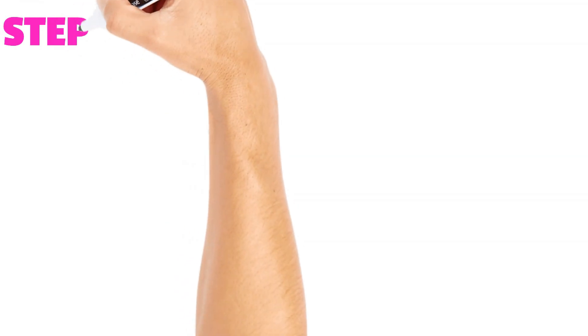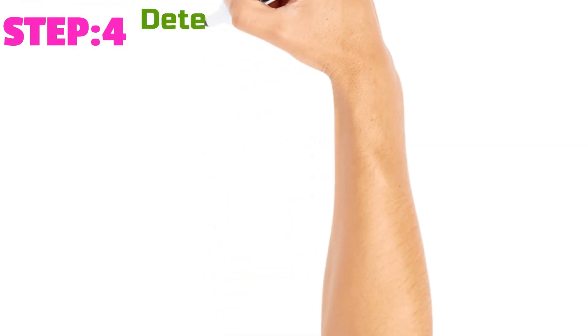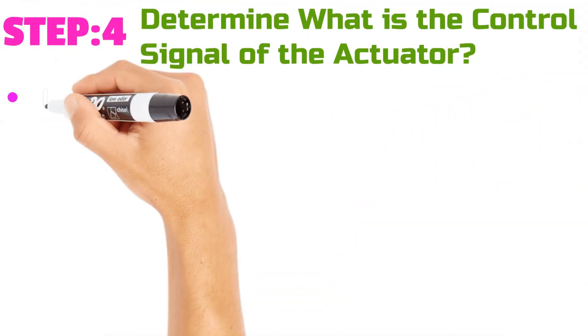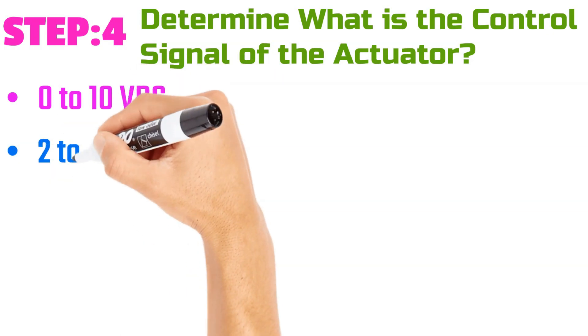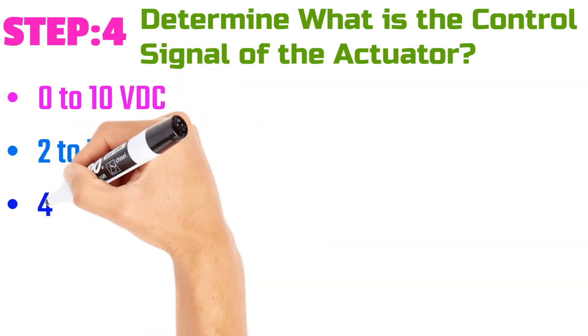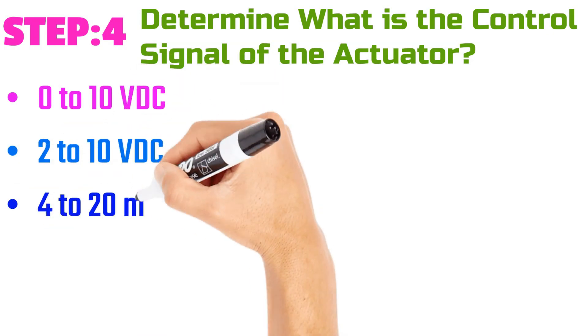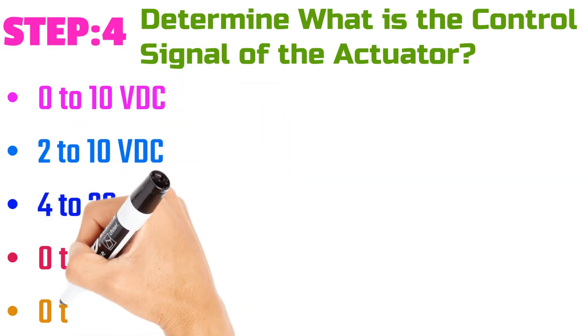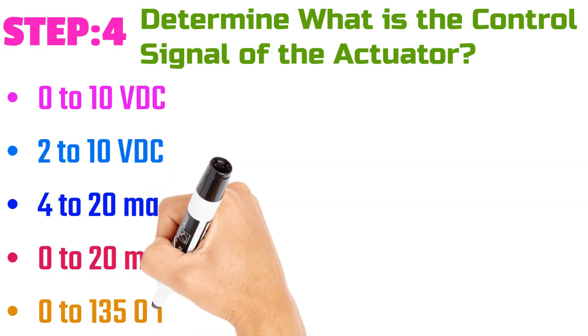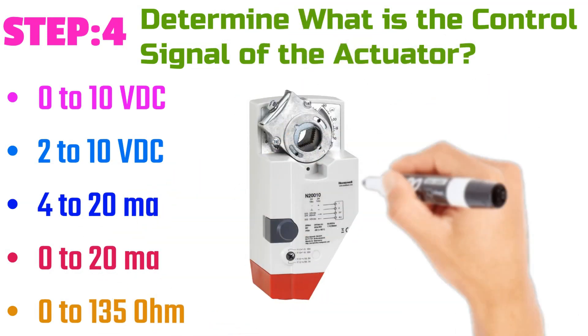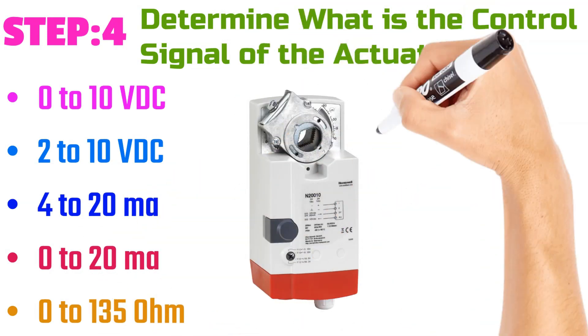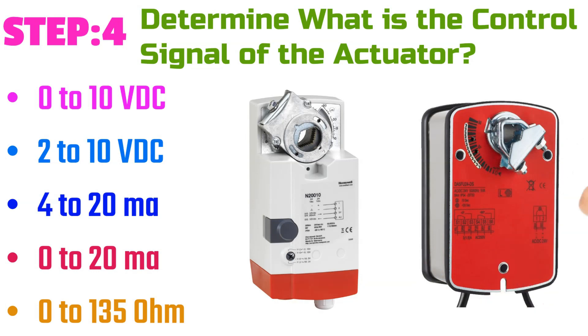Step number four: Determine what is the control signal of the actuator — zero to 10 volt DC, two to 10 volt DC, four to 20 milliampere, zero to 20 milliampere, or zero to 135 ohm.